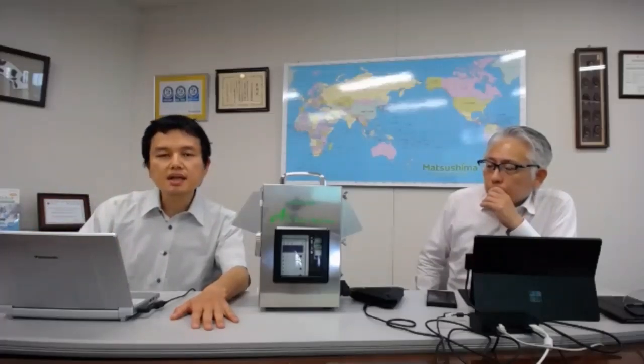Next question: how often should the air dust monitor be maintained? I think this customer is asking about maintenance. It depends on the operation of the facility. Each application has its own maintenance regulation or maintenance cycle. We recommend maintenance whenever there is dust leakage, but for customers using it continuously, we recommend checking the surface for built-up material, and if material is built up, we recommend cleaning it every time.